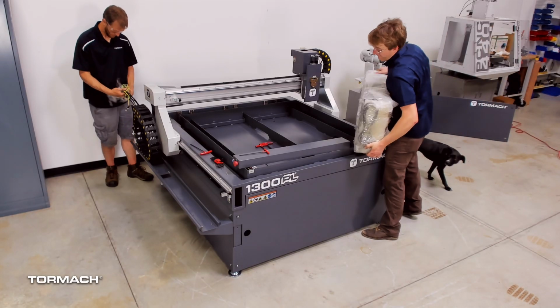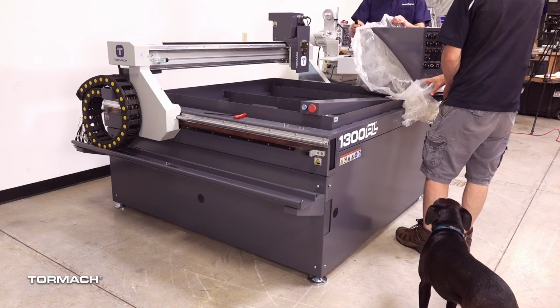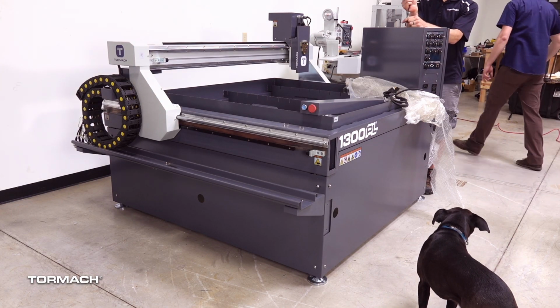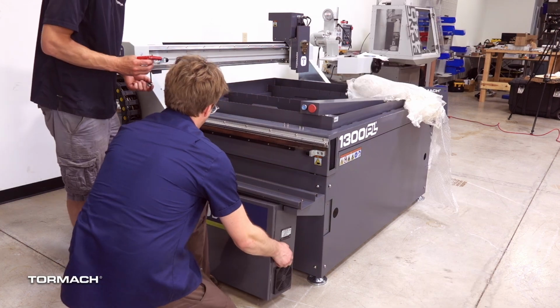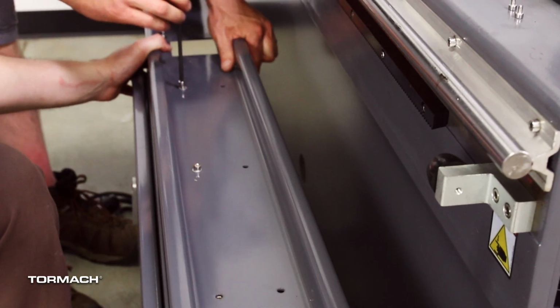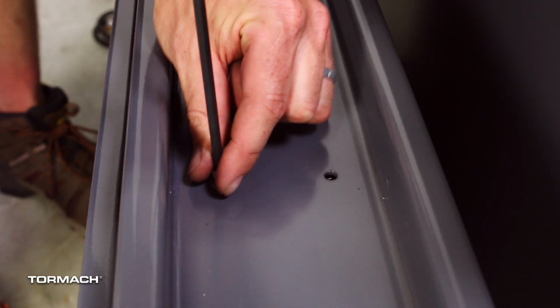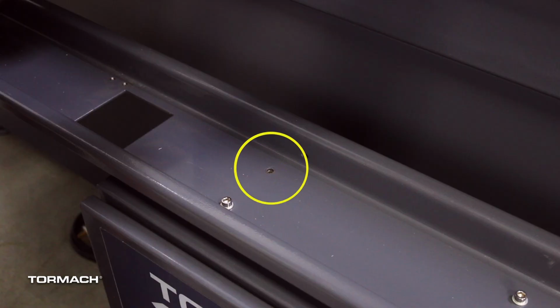Let's grab the electrical cabinet now and get it unwrapped. We'll remove the M6 screws that are pre-installed in it, and use those to mount it to the bottom of the cable tray. While installing this, we want to leave one of the screws out that's closest to the rectangular cutout. We're going to attach a ground wire to this.